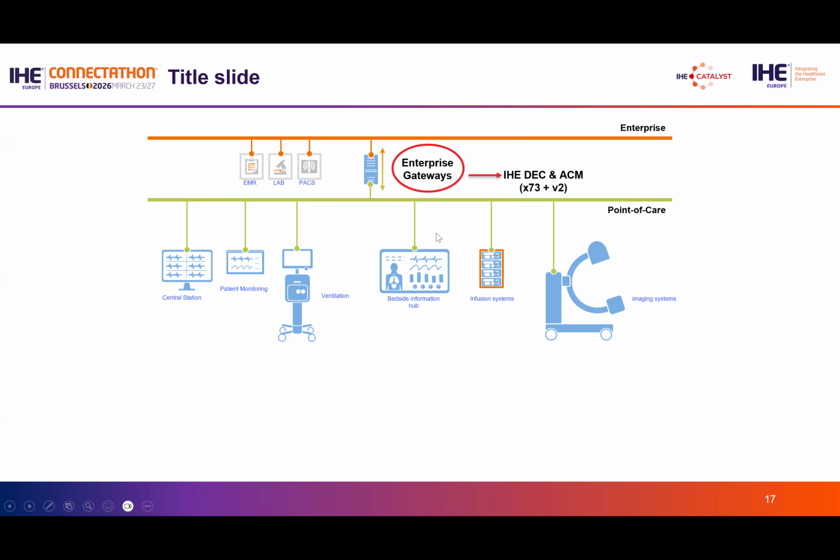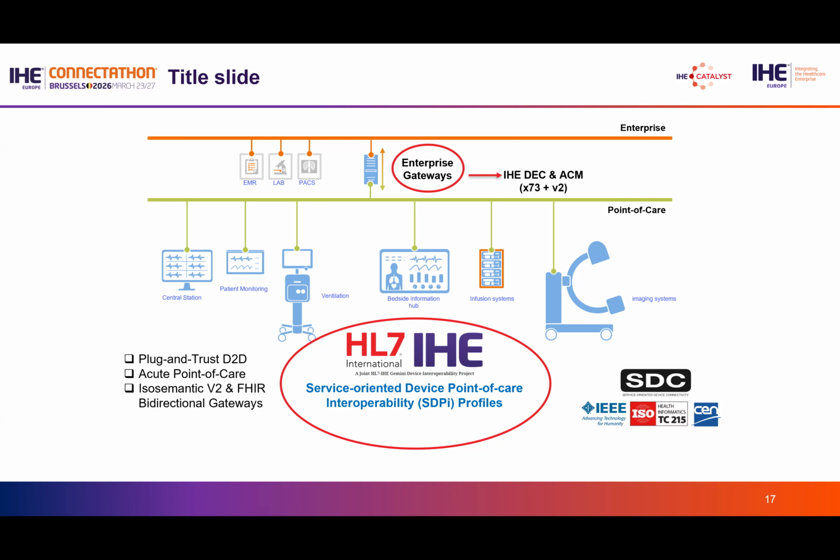But what about the actual devices themselves and how you can get device-to-device plug and trust interoperability? So we have these new profiles that we've defined, service-oriented device point-of-care interoperability profiles. They use the SDC standards, which are IEEE and then also ISO and CEN standard 11073 for service-oriented device connectivity. That's what SDC in this context means for plug and trust, device-to-device interoperability.